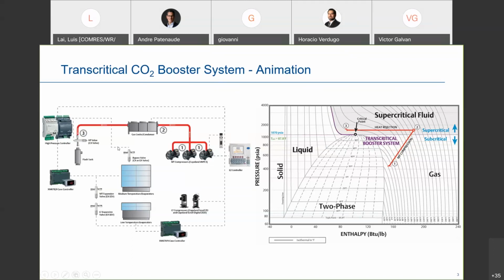Now it goes through the gas cooler on a hot day like I'm showing on the right. It still comes out as a gas. It's just de-superheated, from about 240 degrees Fahrenheit here to somewhere around 100 degrees Fahrenheit. So it took 140 degrees of sensible heat out of it, but it still remains a gas. And the only way to get that gas to turn into a liquid is to drop its pressure enough so that you can hit the saturated liquid line and liquid starts falling out. And that's what this valve between 3 and 4 on the left is there for. It's an electronic expansion valve specifically designed for high pressures. It reduces the pressure from 3 to 4, and in doing so, liquid falls out.